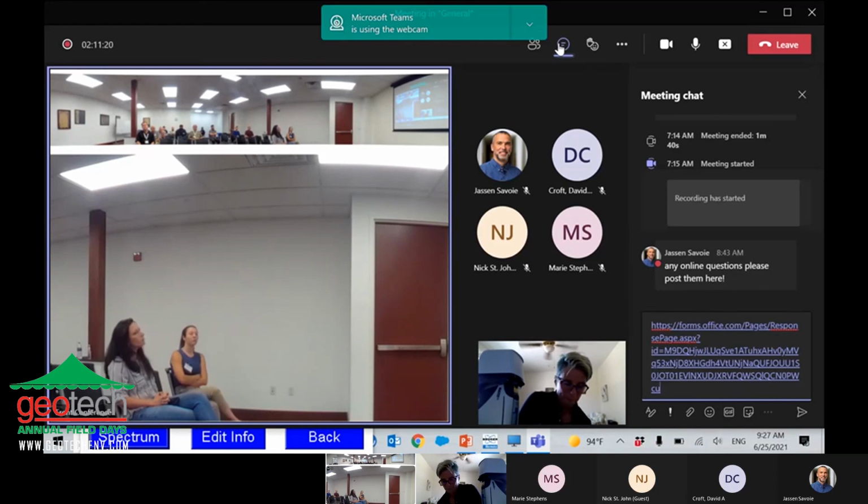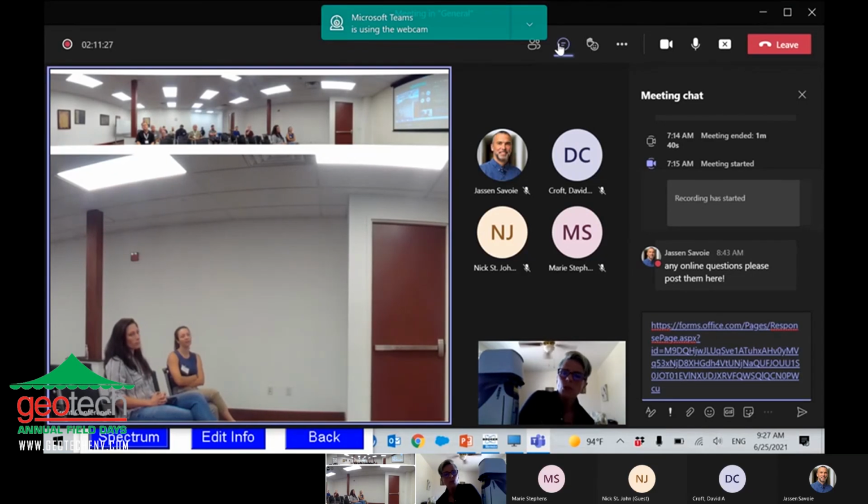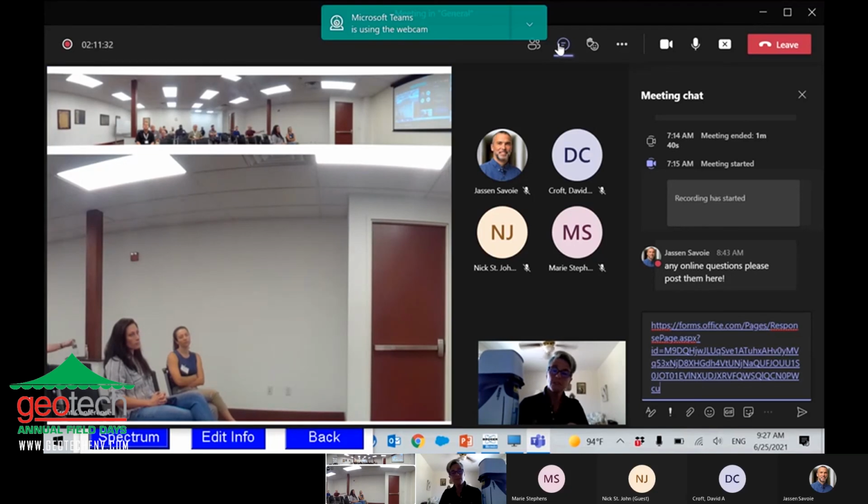Yeah, so when you're calibrating it on the gun, is that just kind of like a setting that you would put it on? What you're doing with the instrument, it comes factory calibrated, and what you're performing is a calibration verification. So for soils, you'll have a soil sample with known amounts in it. You should always request, based on your elements of interest, a standard that comes with it. And this soil, I know that it has 31 ppm lead and 100 ppm arsenic, so that's what I'm looking for.